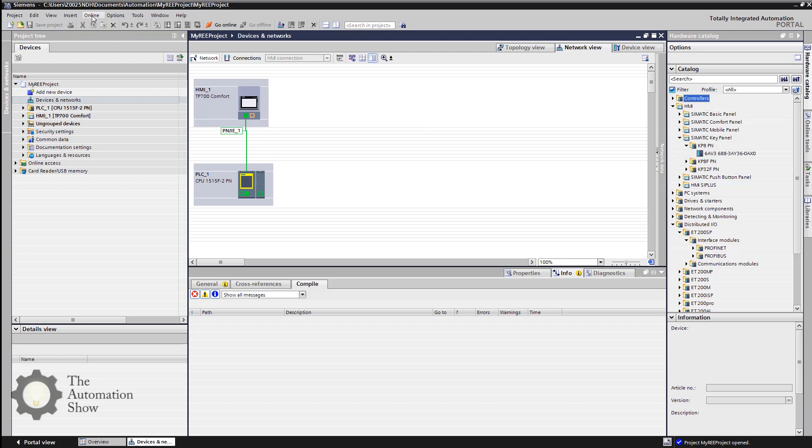We also have the advantage of doing an online detection of these devices. So since we're sitting in front of our hardware in the workshop, we'll do a hardware detection of PROFINET devices. We'll get a dialogue that detects how we want to communicate from our PC out to the network via PROFINET or Ethernet. I'll select the remote I/O device and the key panel device for hardware detection, reading in the firmware revision properties and the configuration of the I/O — digital ins and digital outs. It automatically brings that into my offline project file and represents those in the network view of devices and networks.